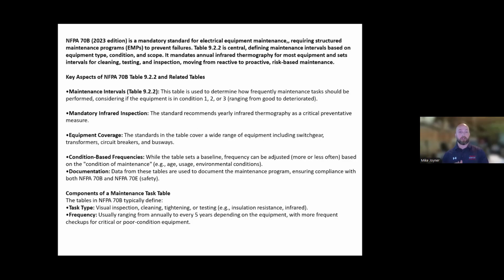These maintenance plans talk about potential intervals. One of the biggest articles I have memorized is from NFPA 70B, table 9.2.2. It clearly defines what pieces of equipment have to be scanned and what scope of work applies, whether it's infrared scanning, energized maintenance, de-energized maintenance, visual inspection, cleaning, tightening, or testing. This table breaks it down into three conditions, and it talks about the frequency of shutting buildings down or doing energized testing, what is mandatory, and what equipment is covered.